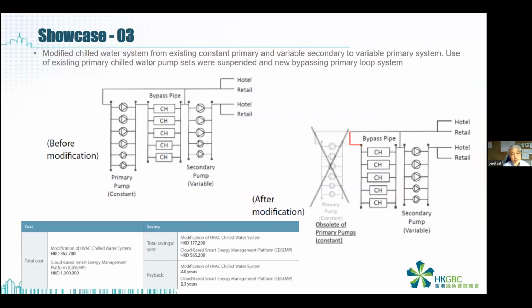Another showcase is to convert the primary, secondary, or decoupler systems into a primary variable flow system. Here they can bypass the primary circuit. They can use a bypass pipe. Because the secondary circuit is variable speed, you just add a bypass pipe here, so that the system will be turned into a primary variable flow system.